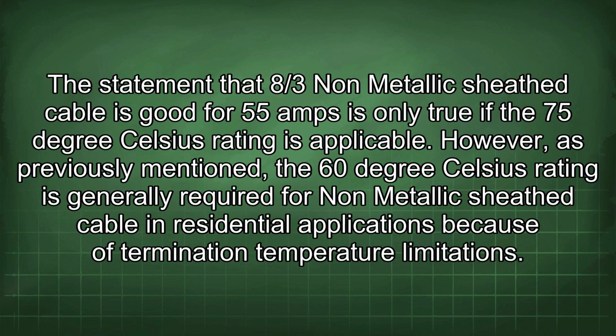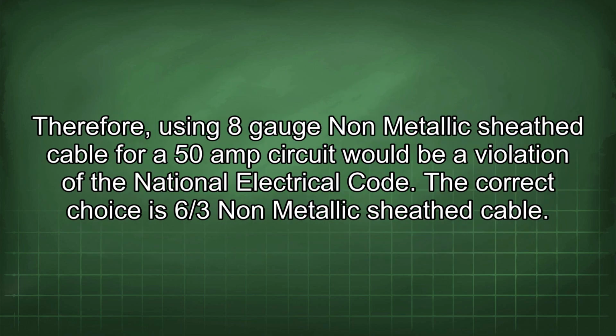The statement that 8/3 non-metallic sheath cable is good for 55 amps is only true if the 75°C rating is applicable. However, as previously mentioned, the 60°C rating is generally required for non-metallic sheath cable in residential applications because of termination temperature limitations. Therefore, using 8-gauge non-metallic sheath cable for a 50-amp circuit would be a violation of the National Electrical Code. The correct choice is 6/3 non-metallic sheath cable.